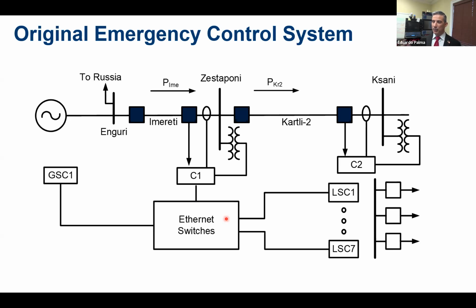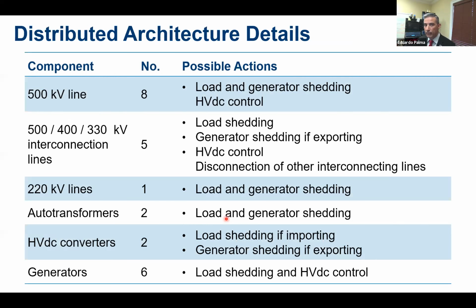Another comment is that protocols that are specifically used for transporting these critical messages to do such an action as to shed load are messages that have to get there within milliseconds. So not any protocol can be used. If I'm not mistaken, this implementation used the IEC 61850 GOOSE protocol in order to exchange values to shed loads. So we used a very interoperable protocol that is available worldwide. Yes, correct. Thank you very much.